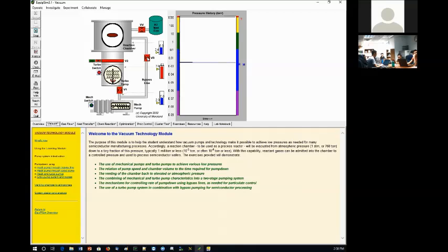Yeah, let's close this valve right now. So since there are no leaks in this ideal world, what happens? It stays at 2.4 millitorr. Do you guys observe that? It doesn't change. Norfolk guys, can you follow me with what I'm doing here?